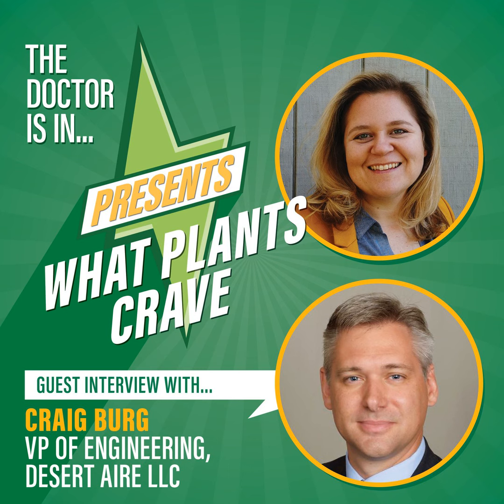Take a look at compressor superheat, subcooling, make sure there's enough refrigerant in the system, that type of thing. I think that should be done once every 3 to 6 months, reviewing all the systems as I mentioned. Engage the manufacturer if you have questions, and get that service tech involved. They're the front line, the person who's going to see the equipment. They should know it just about as well as the manufacturer after a period of time. But if there are questions, engage the manufacturer and ask what tools they have in the toolbox to make this better.